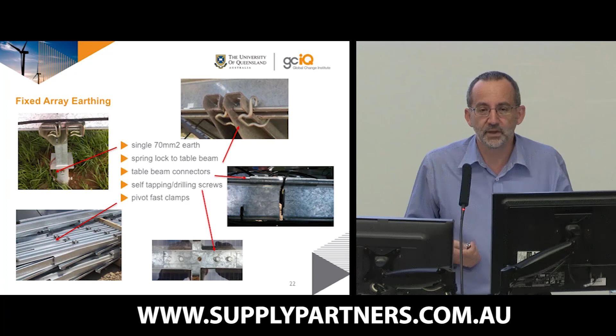So we've also got some interesting earthing arrangements. Going clockwise, we have a single earth on the fixed axis arrays. It's coupled to the horizontal beam by some spring locks, which allow for some lateral movement. That is then coupled along the whole array by some beam connectors, which are held in place by self-tapping or self-drilling screws, which in the smaller systems we're certainly discouraged from using. 5033, in fact, says that's not to be done. And finally, the tables themselves arrive in a folded fashion, which means that the cross rails are pivoting on a bolt, which is another unusual method of earthing. So it remains to be seen how they handle long term.